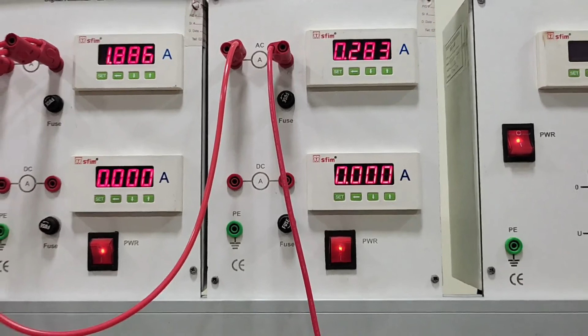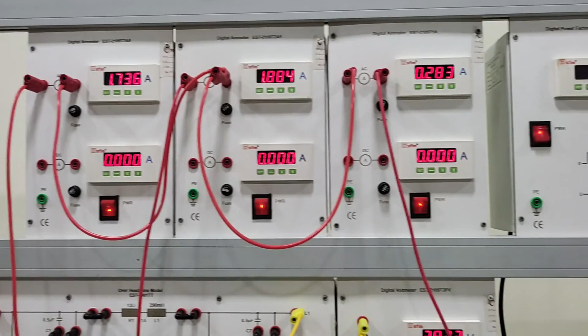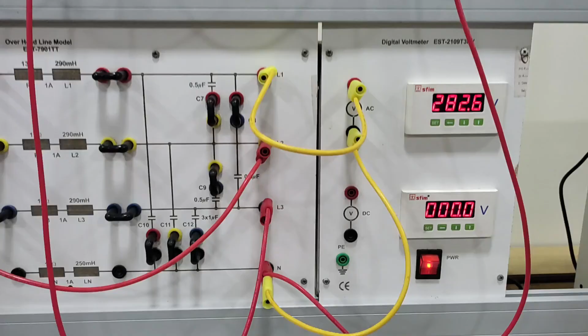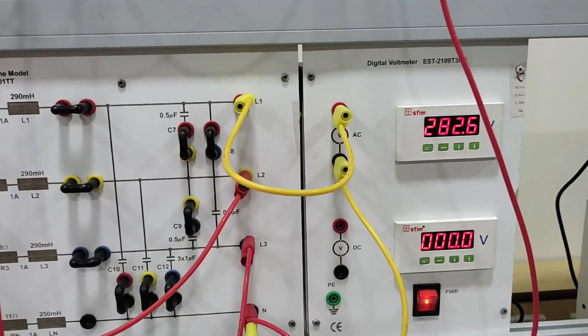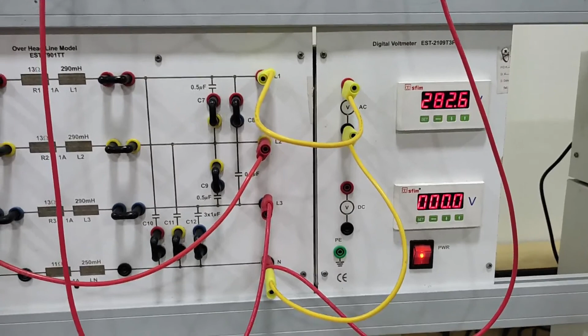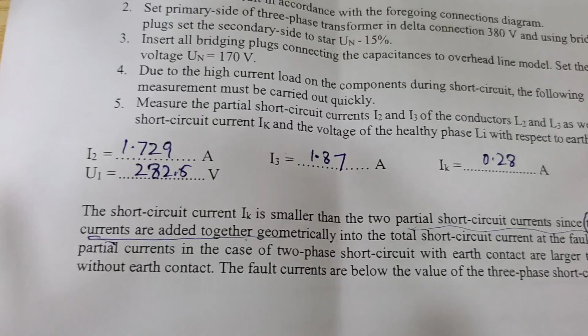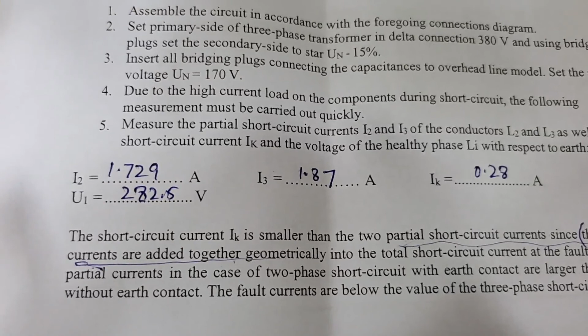So here this is the current for phase L2, and this is the current for phase L3, they are almost the same. And this is the earth fault current, that is 0.28. So students, you can see that the earth current is the minimum as compared to the phase currents. You can also see here the voltage of the healthy phase is 282.6 volts, and for the rest of the phases it will be 0 because they are short circuited. And students, now we will note down these readings in our manual. Here you can see that we have noted down the readings.